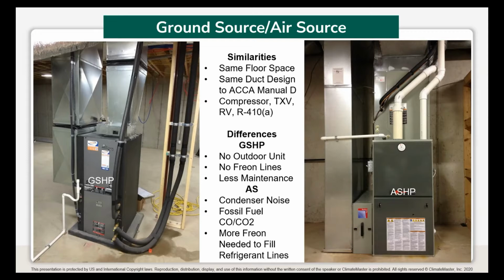Each one of these technologies takes up the same floor space. They both operate using the exact same compressor. It could be a single stage Copeland scroll, or a two-stage Copeland unloading scroll compressor. We use exactly the same thermal expansion valves, same reversing valves, same refrigerants. The only difference between the two technologies is that the ground source heat pump has no outdoor unit. It has no freon lines running from the condensing section to the evaporator coil. And really, because of those facts, it has less maintenance.